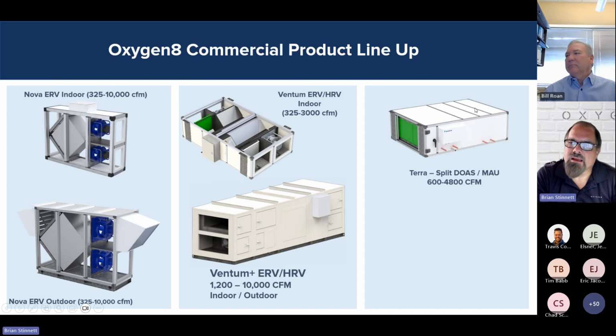And finally, we make a split DOAS unit. Can be hot water, chill water, or could be VRV DX, but it's 100% outside air, what I call brute force heating and cooling. No energy recovery. Use this for kitchen makeup. Use it for makeup air when I've got, let's say, fume hoods or separate exhaust. But it's 100% outside air with, like I said, chill water, hot water, and or VRV DX heating and cooling.